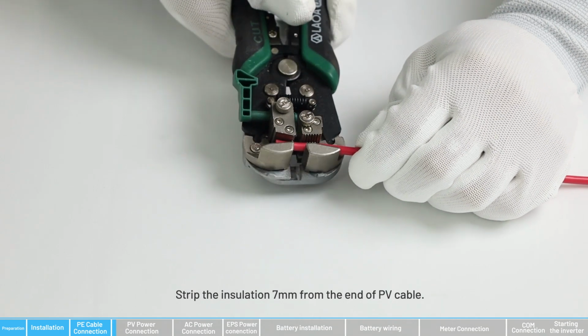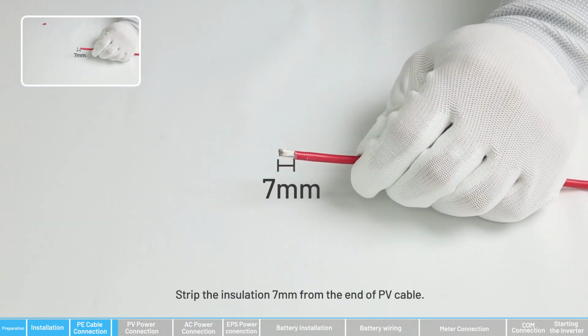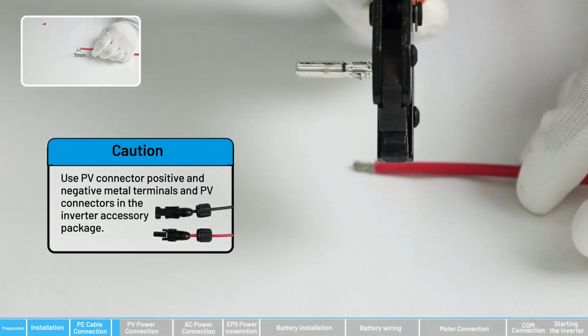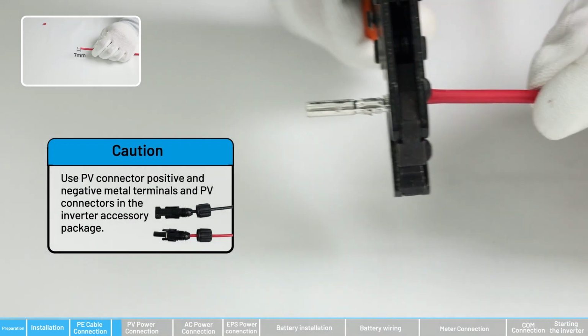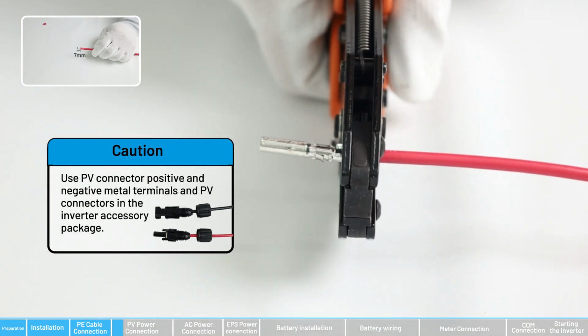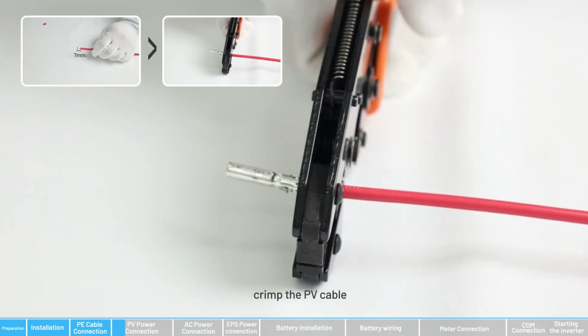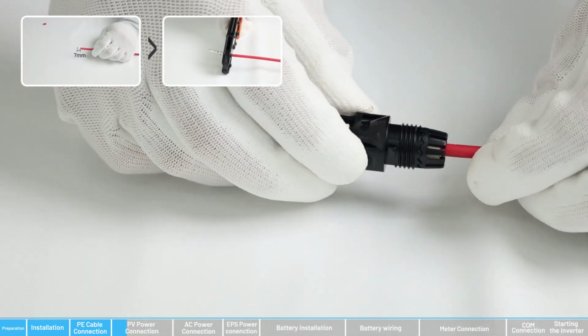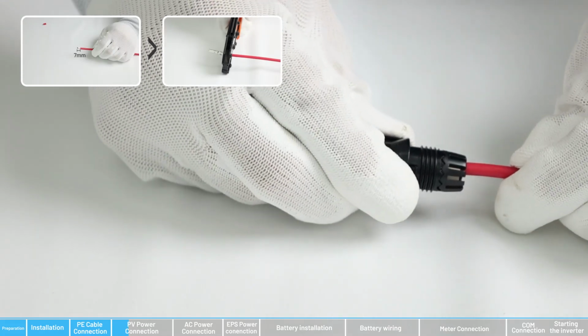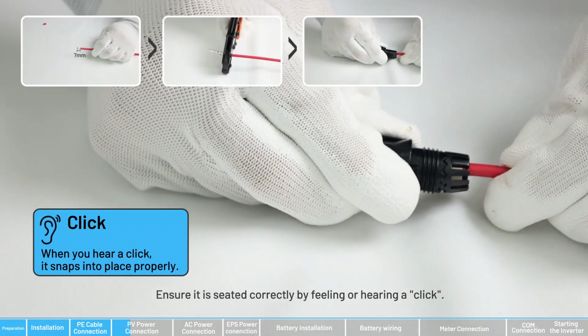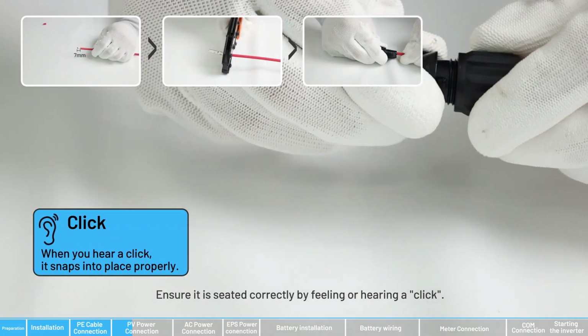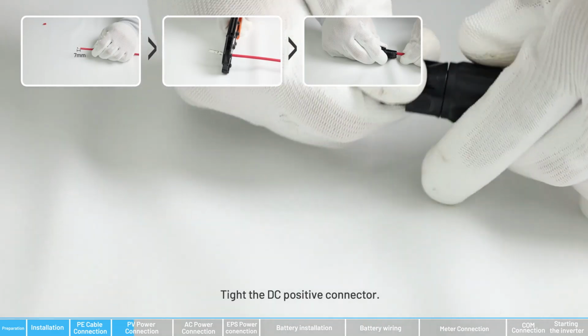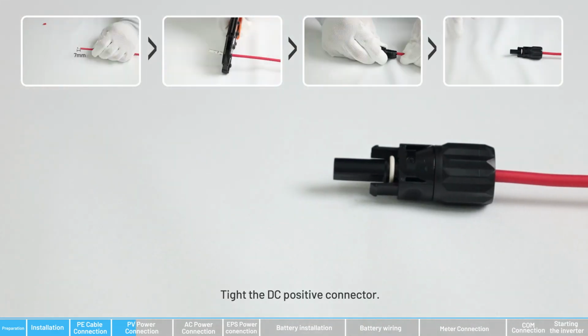Strip the insulation 7 mm from the end of PV cable. Crimp the PV cable. Ensure it is seated correctly by feeling or hearing a click. Tighten the DC positive connector.